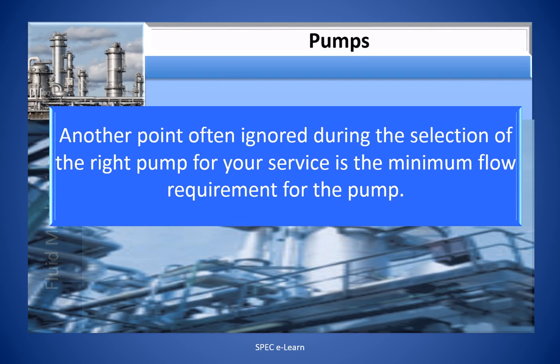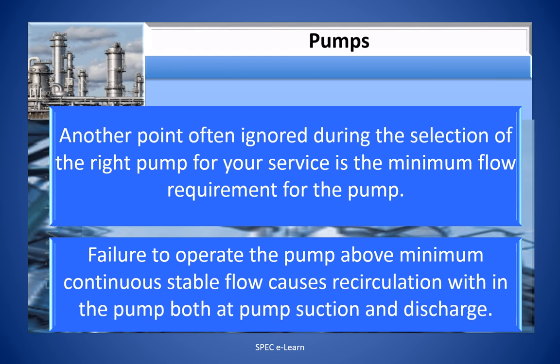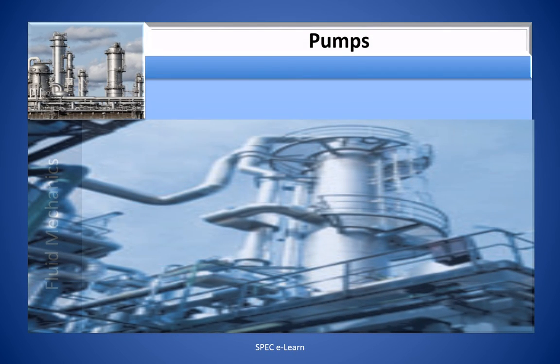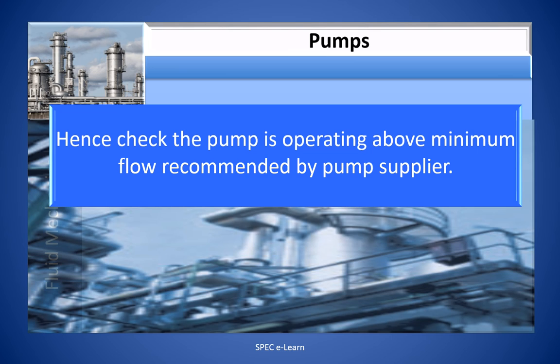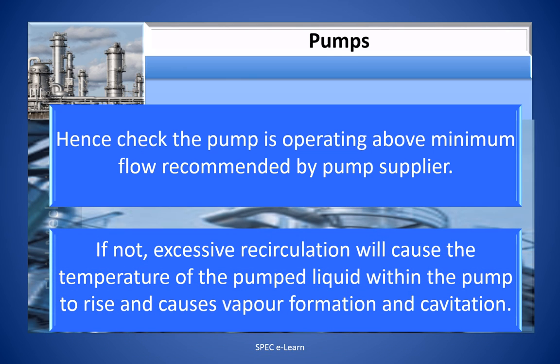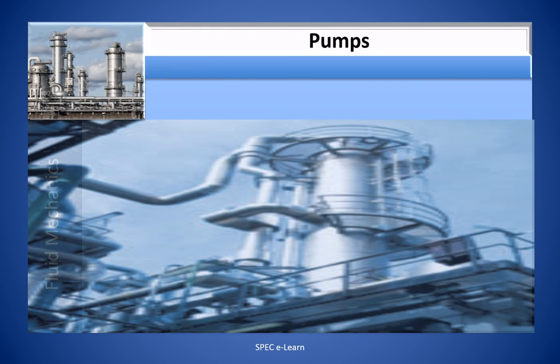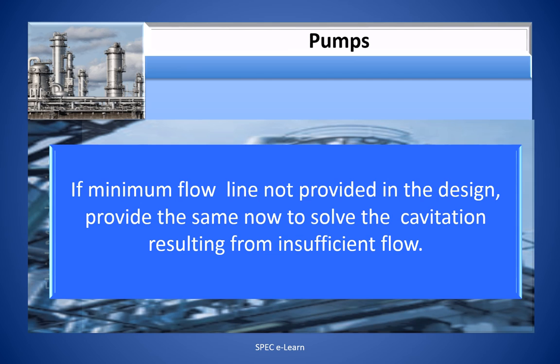Another point often ignored during pump selection is the minimum flow requirement. Failure to operate the pump above the minimum continuous stable flow causes recirculation within the pump at both suction and discharge. Hence, check that the pump is operating above the minimum flow recommended by the pump supplier. If not, excess recirculation will cause the temperature of the pumped liquid within the pump to rise, causing vapor formation and cavitation. If a minimum flow line is not provided in the design, provide one now to solve the cavitation resulting from insufficient flow and recirculation.